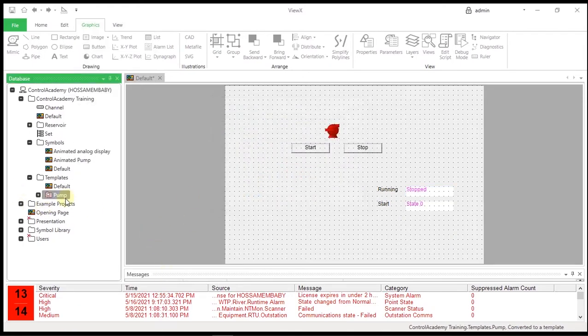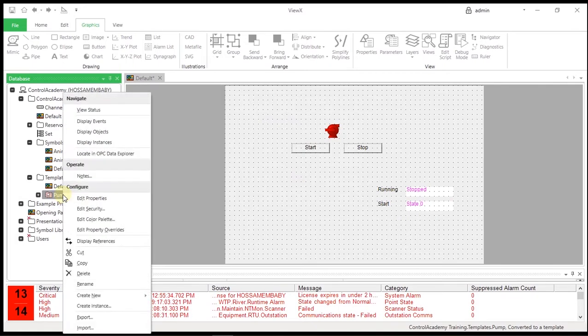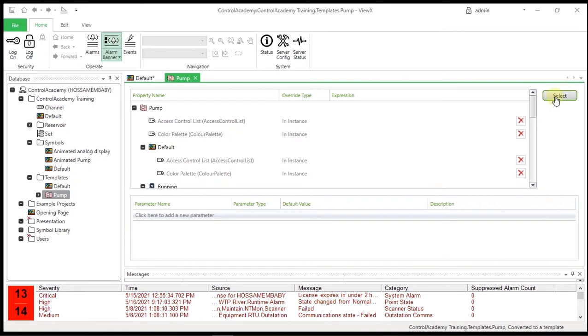Now let's talk about overriding template settings. Right-click on the Pump Template object and select Edit Property Overrides from the menu. Property Overrides allow you to override the configuration settings that are defined in a group template. This allows group instances to take their configuration from a template but have some unique properties.